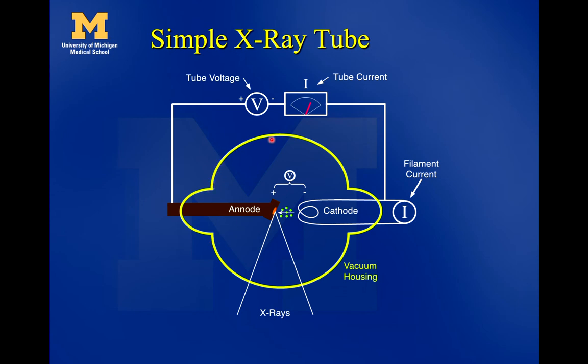All x-ray tubes function in a vacuum. We have this vacuum housing around the x-ray tube. They suck all of the air out so that when the electrons are traveling from the cathode to the anode, they can do so without running into any air molecules or losing any energy. Most things produce an electron beam using a hot cathode. In the x-ray tube, it's usually a spiral of tungsten — it looks almost like an incandescent light bulb.